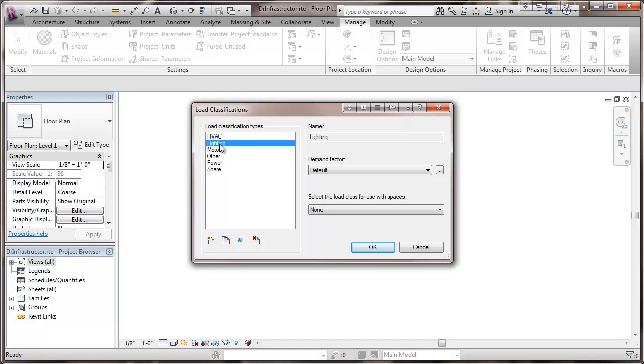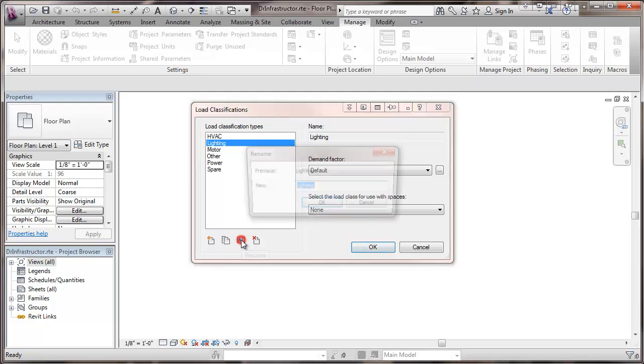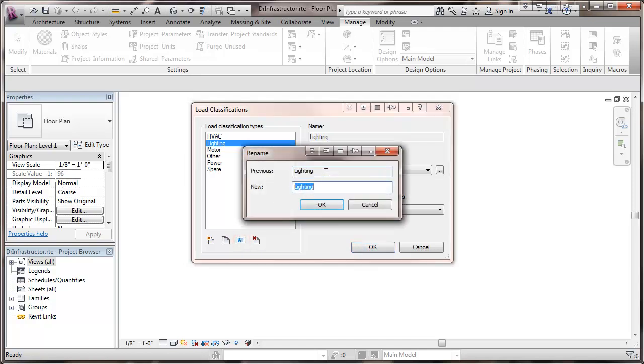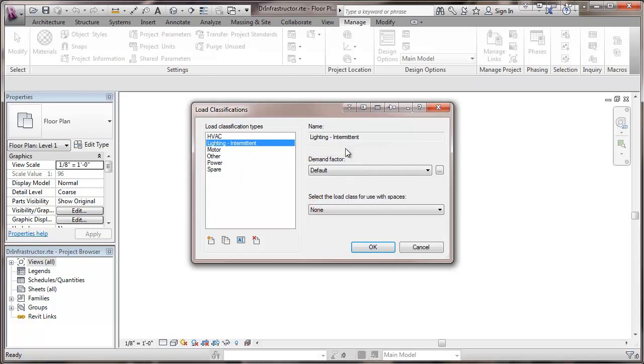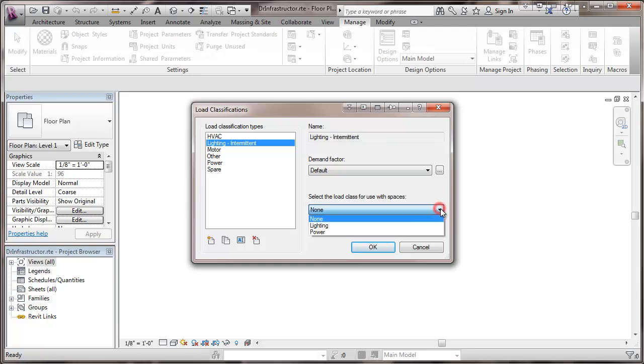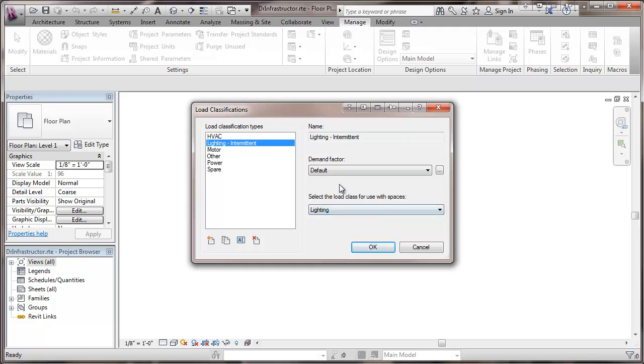Under the lighting we're going to change this a little bit. We're going to show two different kinds of lighting. We're going to rename this one and this will be intermittent. And that intermittent lighting is lighting that's not on for longer than three hours, so stuff that's on occasionally in a storage space or something controlled by an occupancy sensor would be in that intermittent category. And we're going to assign this as the lighting load for space.